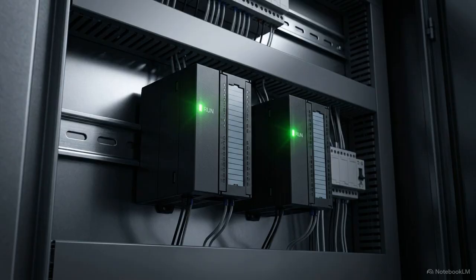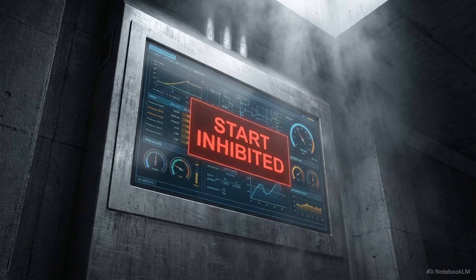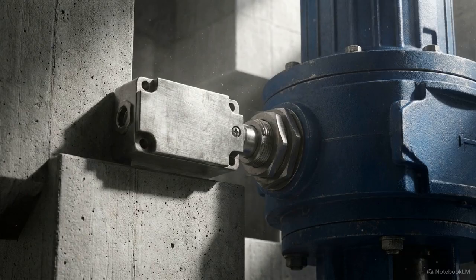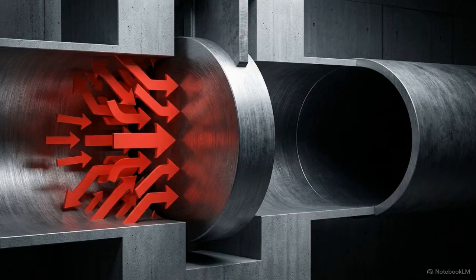When the plant is ready to pump, the digital start command originates from a hot standby programmable logic controller panel containing two identical parallel CPUs. But the PLC will refuse the command without a physical prerequisite. A hardwired interlock verifies via limit switches that the massive 600mm discharge valve is fully closed. The pump must start against a closed head to keep initial torque demands low.